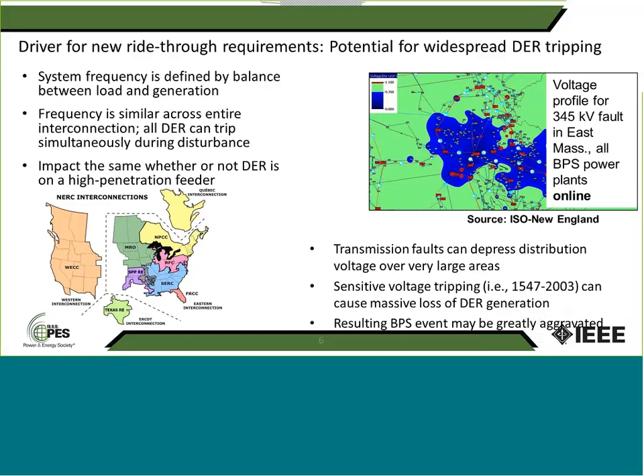So they raised this concern with the utilities under the Massachusetts Technical Standards Review Group, and I'll walk you through the adoption process later on. But one thing that you may ask is, if I have a fault on a 345 kV line, the faults on the transmission system can be cleared pretty fast, way before even DERs may trip. So why are we even worried about this issue? Well, you're absolutely right that the fault can be cleared by high-speed protection, like a zone 1 of a distance protection, and the relay itself can trip immediately, plus you'll have just one cycle, or even a fraction of a cycle, for breaker operation on the transmission system.